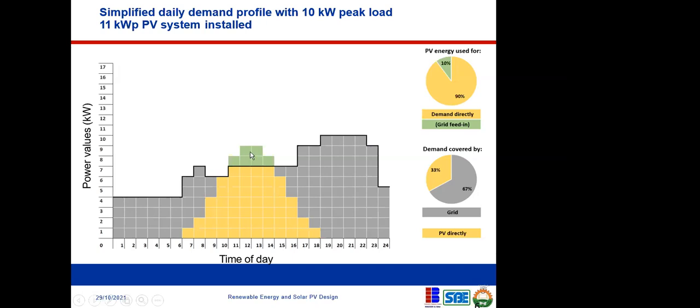So you've exceeded it. The problem here is that if you do this kind of design and you're having this excess power from the sun and you don't have a battery storage system, it actually goes to waste. So this is over design. The system can be said to be over design unless you have a battery system that can absorb this. But in this case, it is assumed that it is connected to the grid.